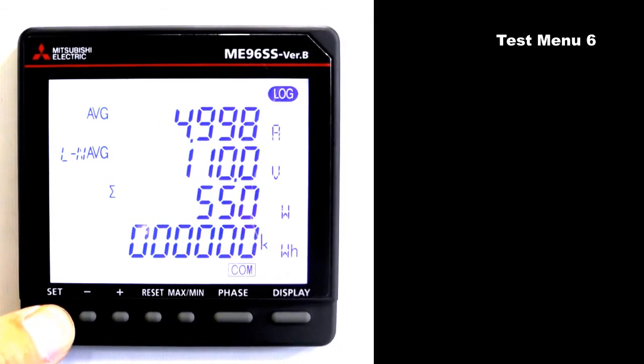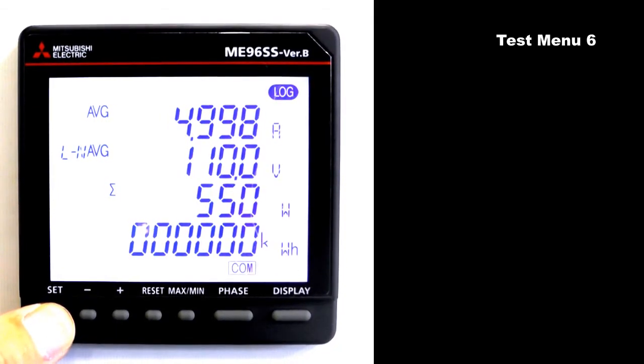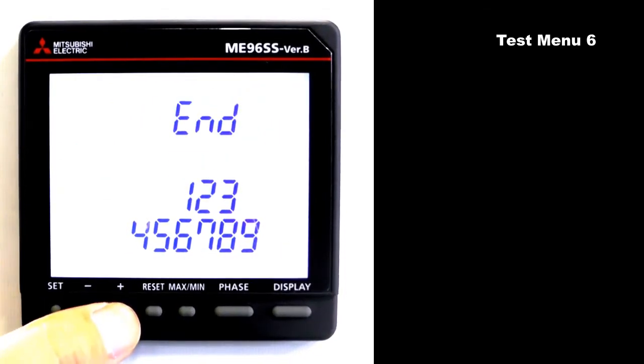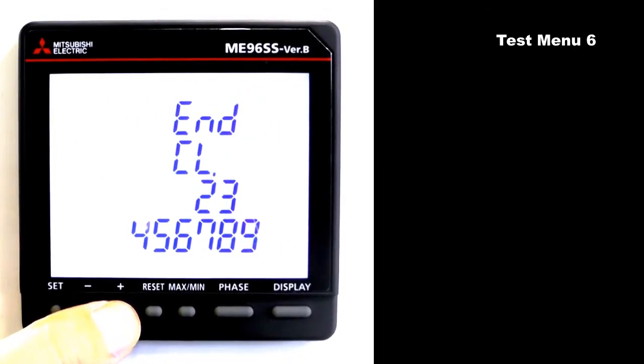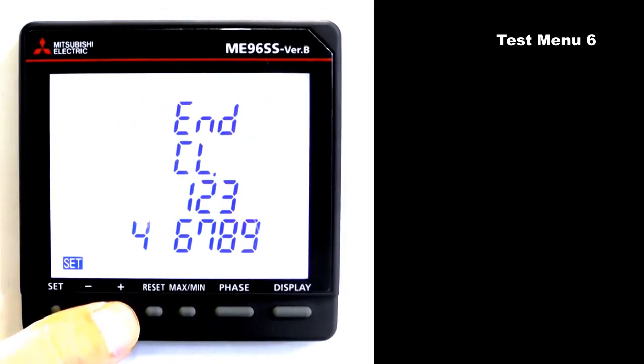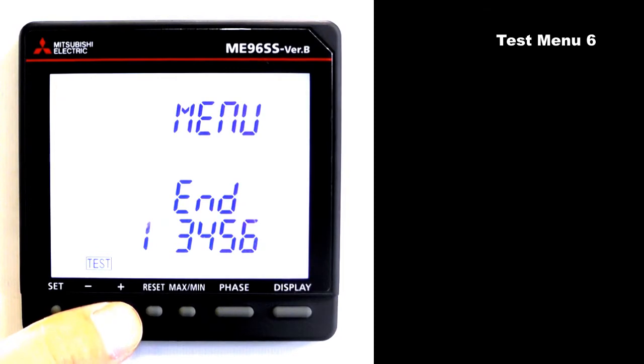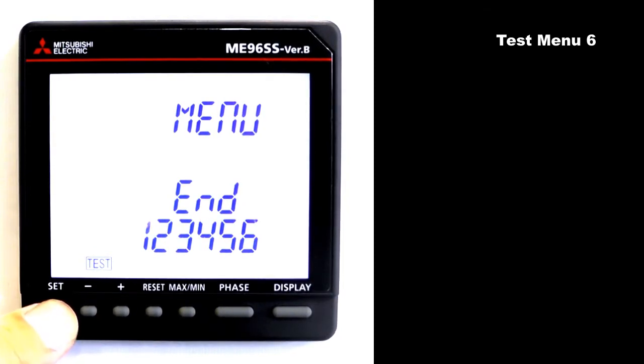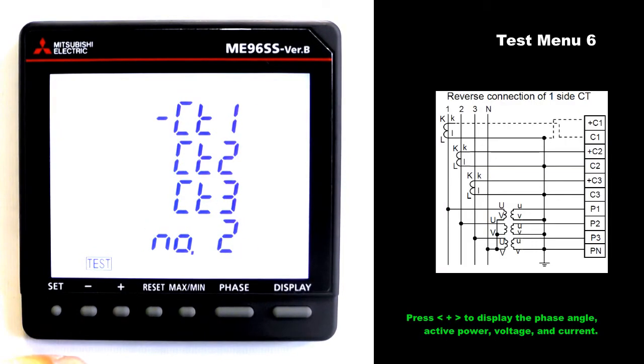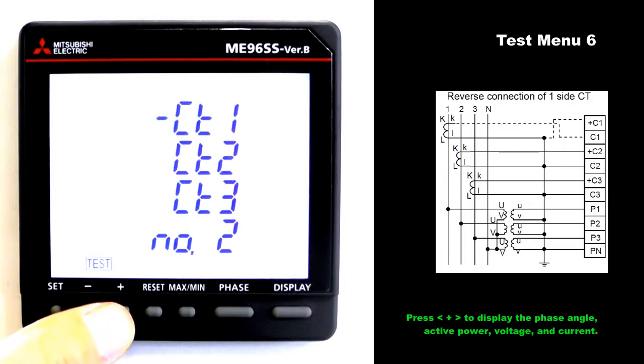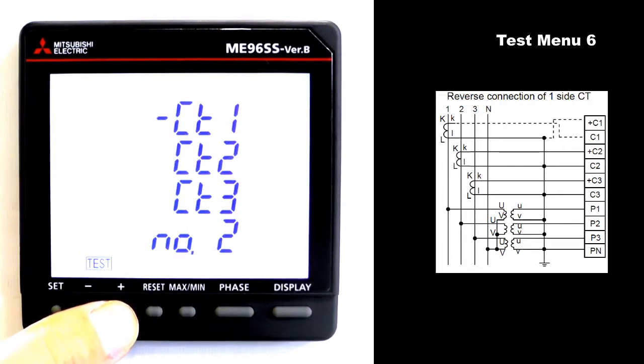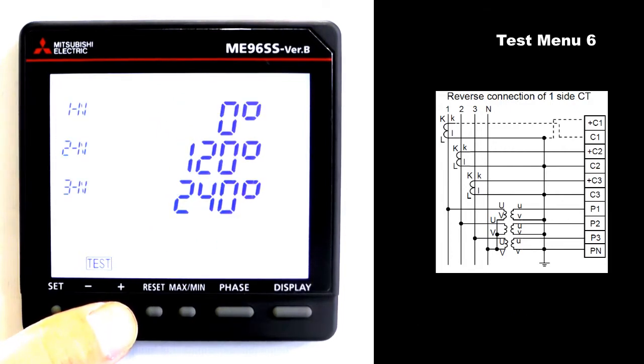Press and hold set for 2 seconds. Press plus to blink 9. Press set to move to the test menu. Press plus to blink 6. Press set to move to test menu 6. Next, this is an example of one side CT reverse connection.